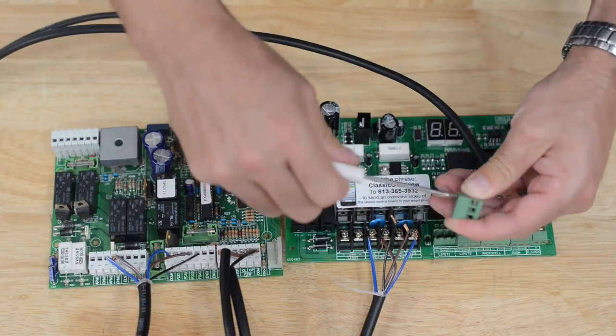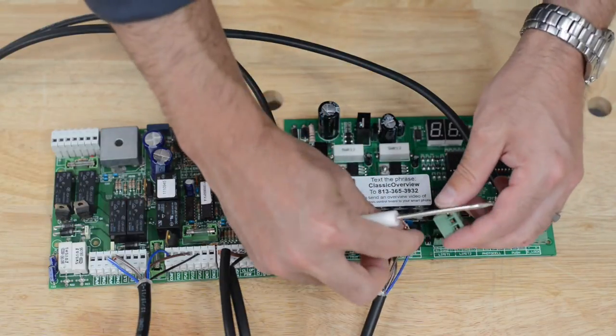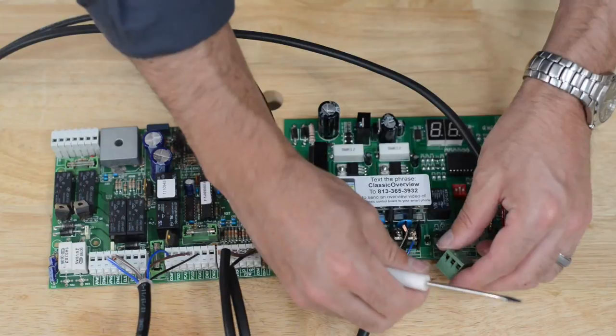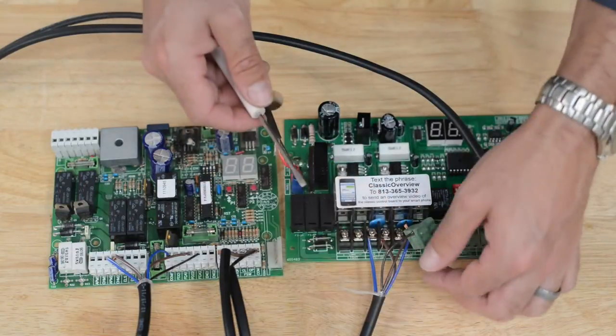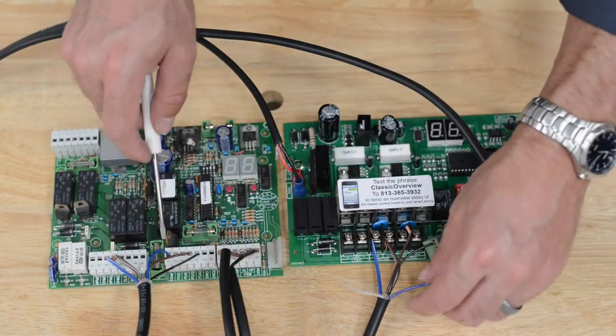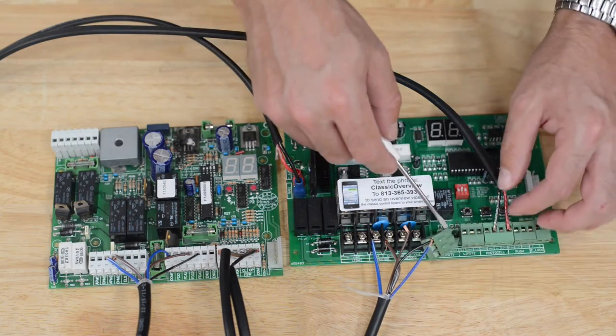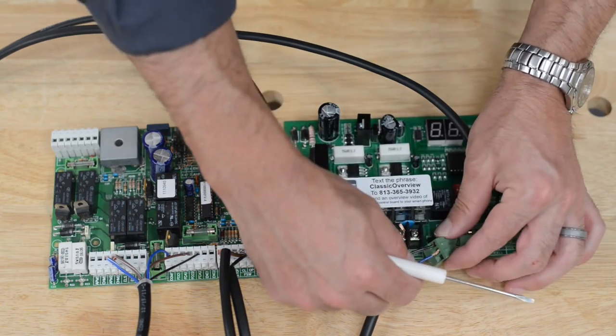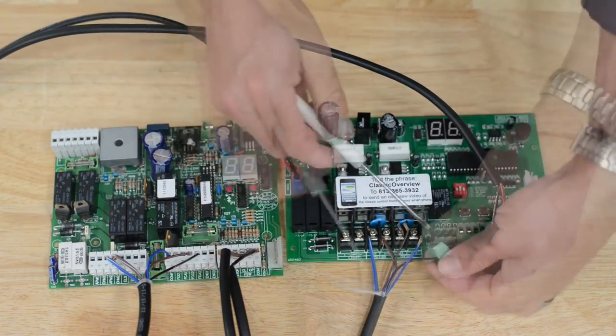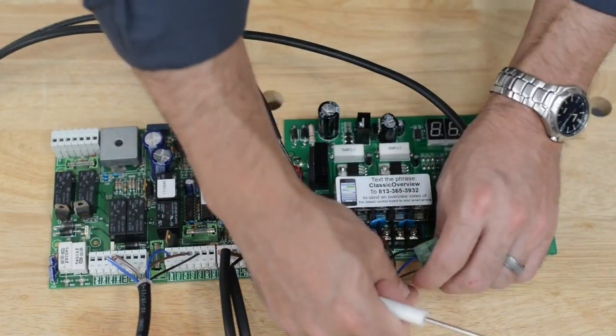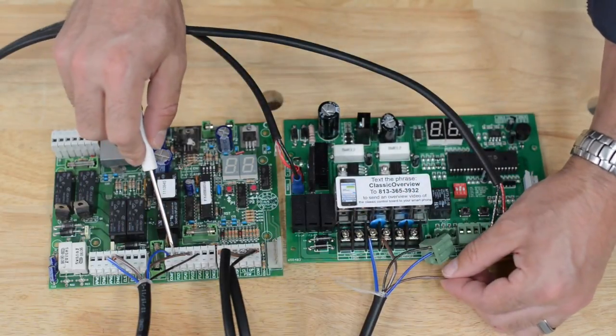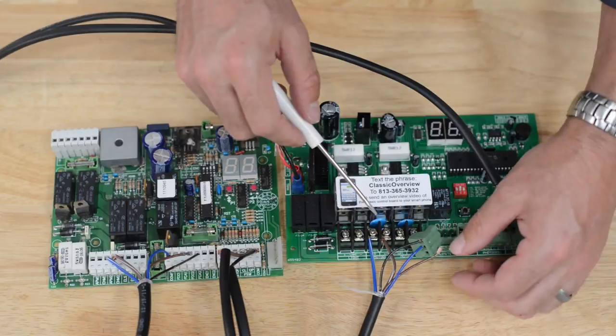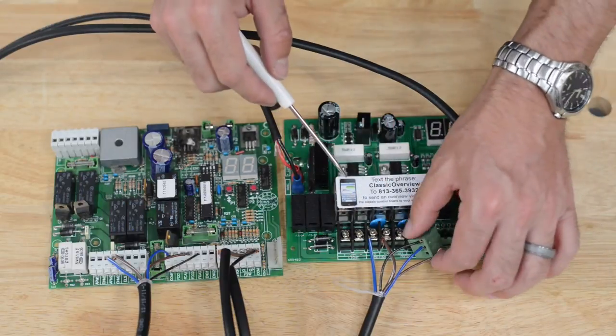This being the open limit. FCA on your old board is open limit. The blue wire was in this first one COM-F. It is going to go into COM-1 on this side. And lastly, the brown was an FCC1, which is your closed limit. On this side, we're going to put it into CL1.